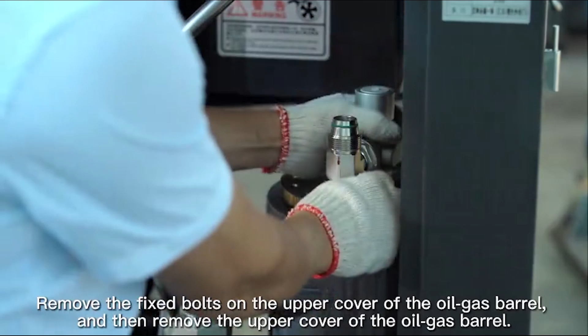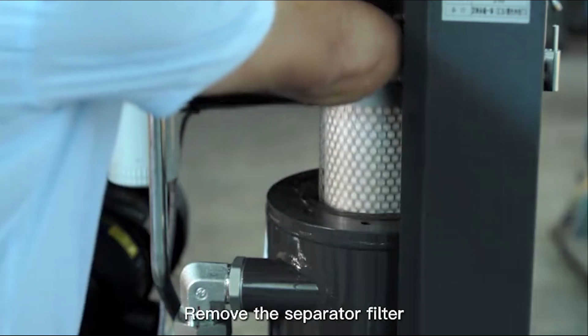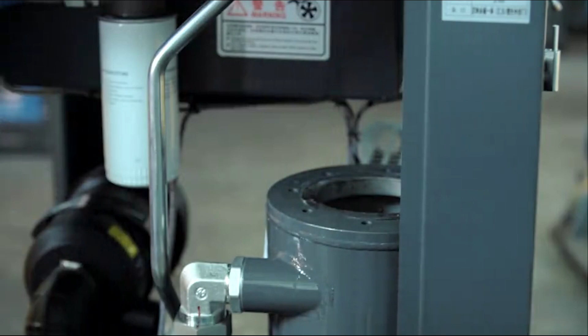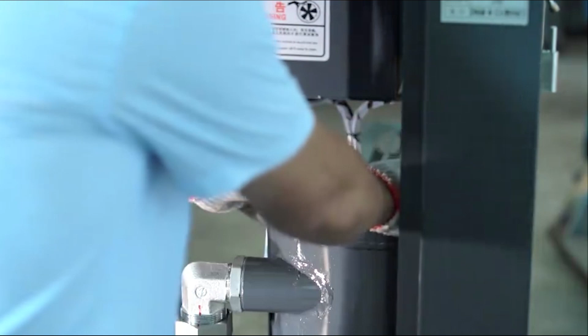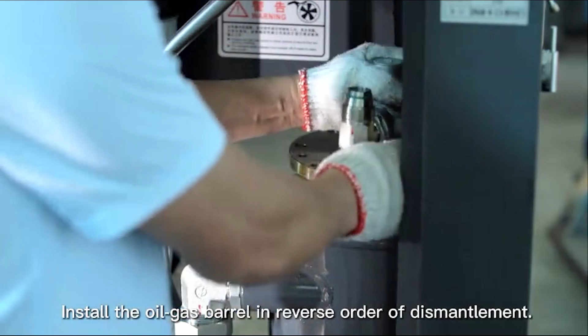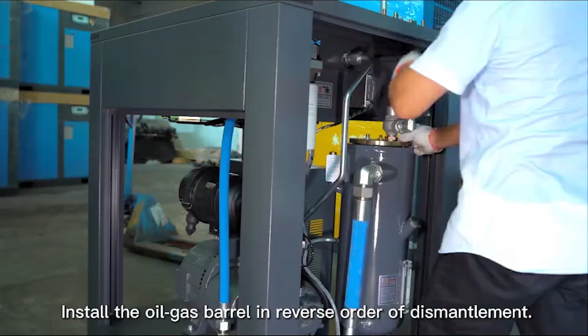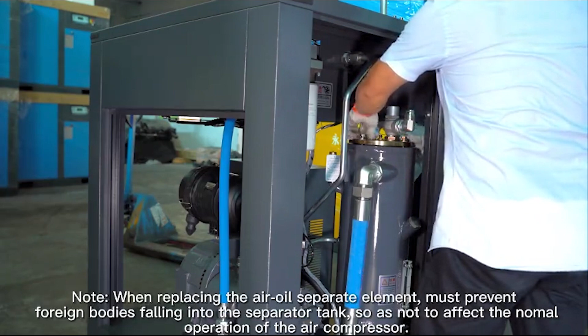Remove the fixed bolts on the upper cover of the oil gas barrel, and then remove the upper cover of the oil gas barrel. Remove the separator filter. Replace with a new one. Install the oil gas barrel in reverse order of dismantlement. Note, when replacing the air-oil separator element, you must prevent foreign bodies from falling into the separator tank so as not to affect the normal operation of the air compressor.